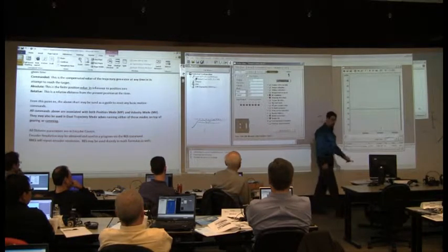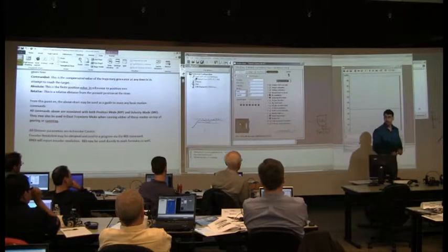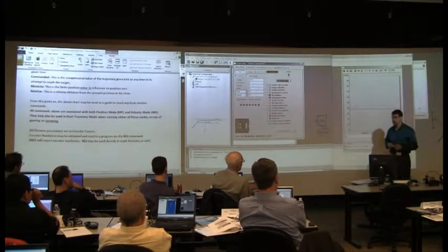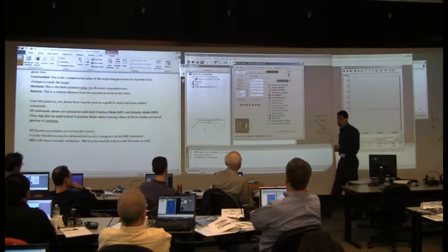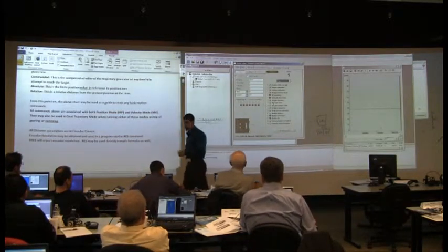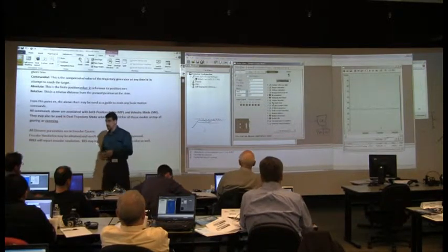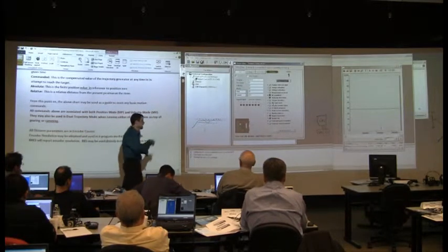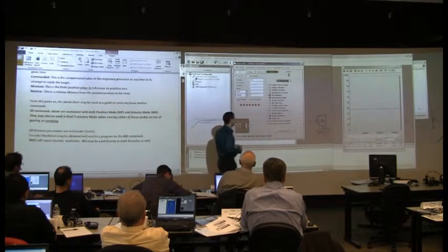Okay? Wraparound occurred. Anybody have an idea what wraparound means? Nobody? That's 32-bit max counting what we have on the internal encoder. Plus or minus 2 to the 31st, plus or minus 2.1 billion encoder counts. Anytime you wrap over that, that wraparound will occur.